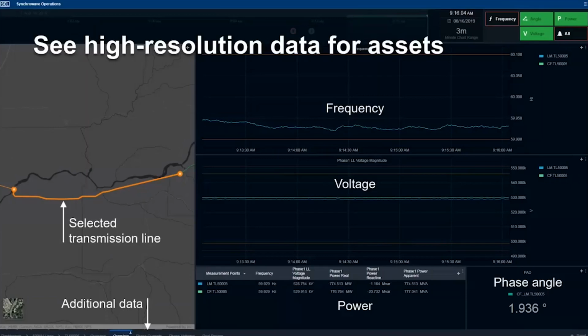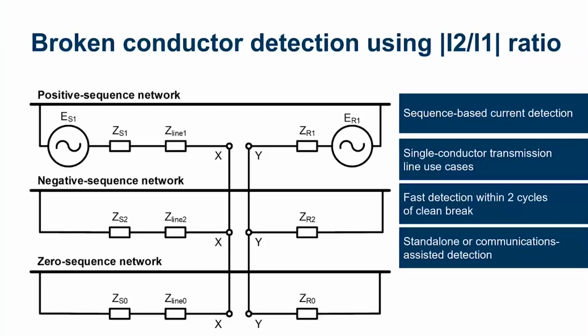Okay, so we are going to continue on with our discussion on ways to detect broken conductors and mitigate wildfires on transmission lines. Something Anthony already brought up was using the I2 over I1 ratio to detect a broken conductor. That works pretty good, but the only problem is that, as we can see here on our sequence networks, this is going to be highly dependent on what our Z0 is. So let me rewrite that: I2 over I1, and we can derive that to be our Z0 total divided by Z0 total plus Z1 total.